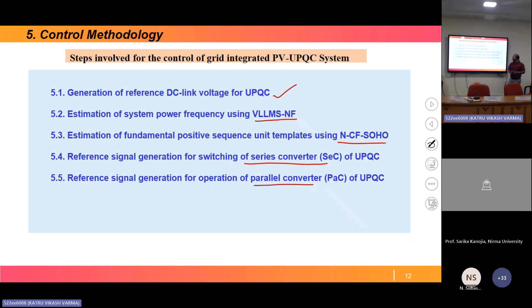Then coming to the first one, that is the reference DC link voltage. The DC link voltage, all of us know, plays a pivotal role in the coordinated control of both the converters. Since both the converters are connected across the DC link, this DC link voltage is to be maintained always, otherwise there will be mal-operation. And this DC link voltage must always be greater than the peak value of the grid voltage for the controlled switching of the inverters.